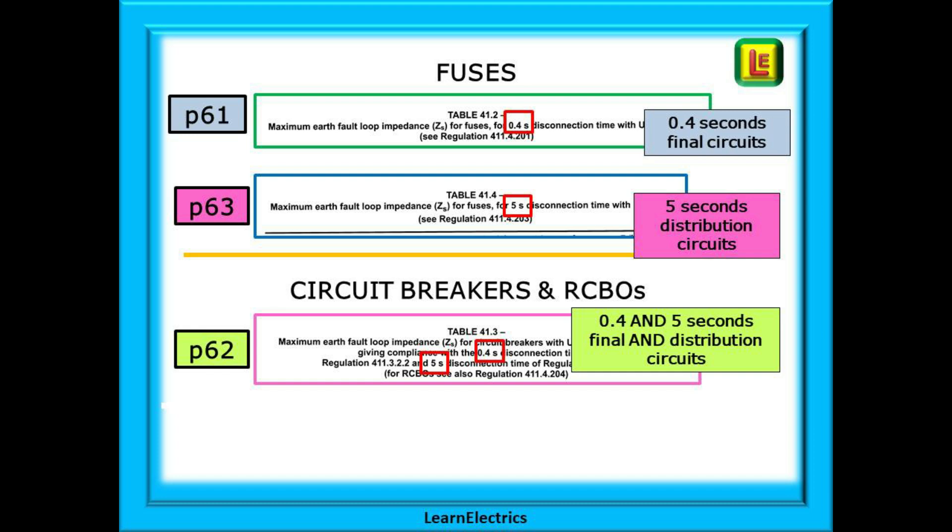The tables on page 61 and page 63 are to do with fuses. Page 61 is for fuses in final circuits with tripping times of 0.4 seconds or less. Page 63 is for fuses in distribution circuits with tripping times of 5 seconds or less. For fuses we use a different table for different tripping times.